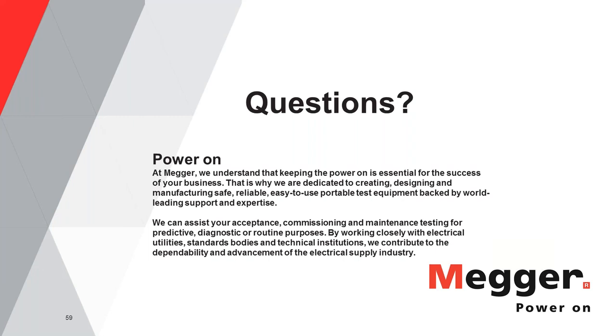And just as you said, if you don't have a big enough field test set to get that current, then you'll obviously need to reduce the instantaneous pickup. The ideal thing is to keep it as close to what it would be set at when it's in operation. But if it's not possible to achieve that level of current using your field test set, then you will need to reduce the pickup to a smaller value.